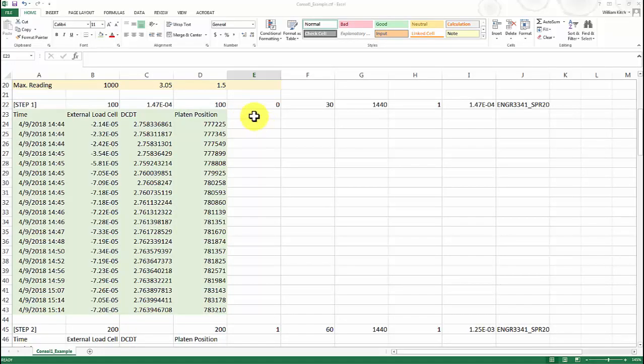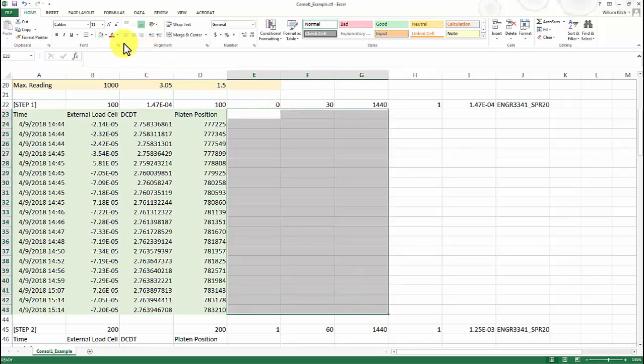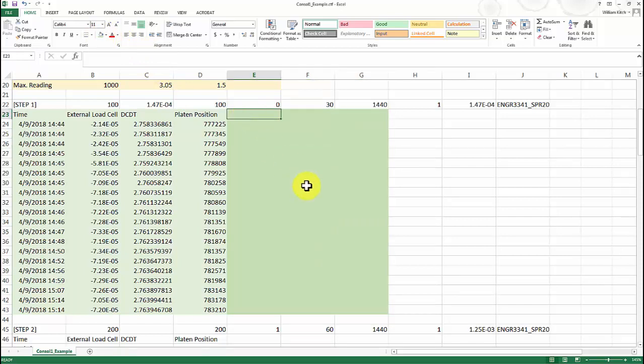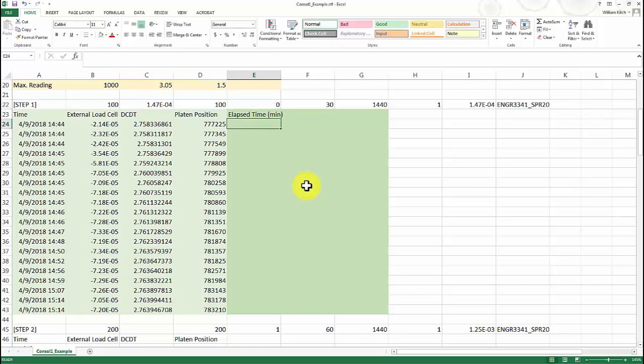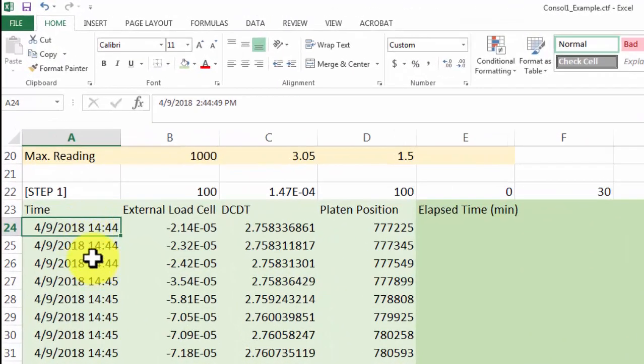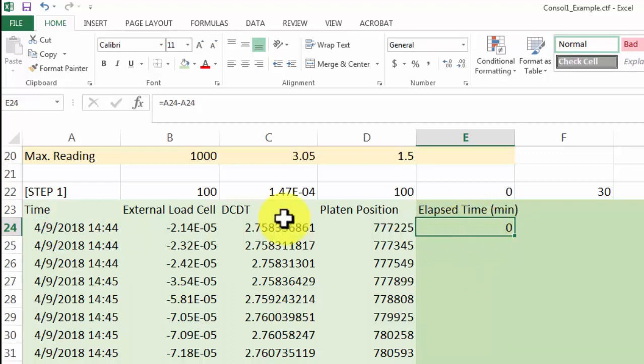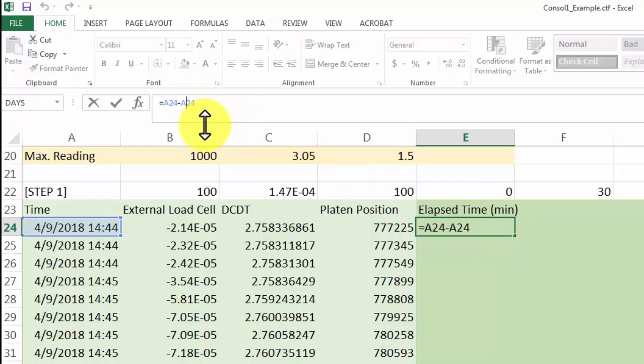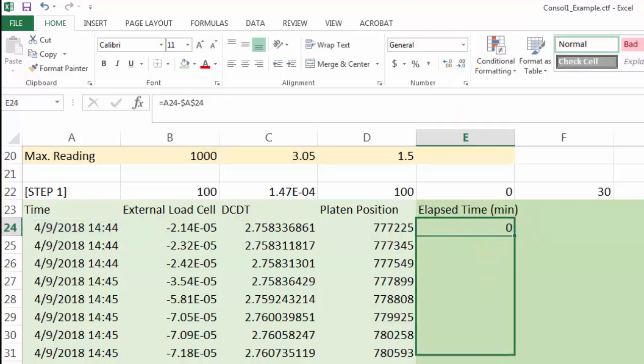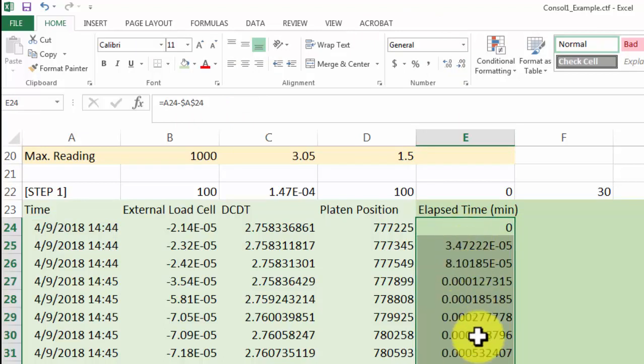So now we're ready to start our conversion. We're going to insert our engineering-converted values out here in this section, highlighted with a slightly darker green. The very first thing we want to do is determine the elapsed time for each reading — this column will be the elapsed time column, in minutes. To get the elapsed time, we subtract the starting time in cell A24 from each of the other times. Entering that formula gives us an elapsed time of zero for the first reading. We lock in cell A24 with a dollar sign so that when we copy the formula down, the elapsed time always references back to that zero time.